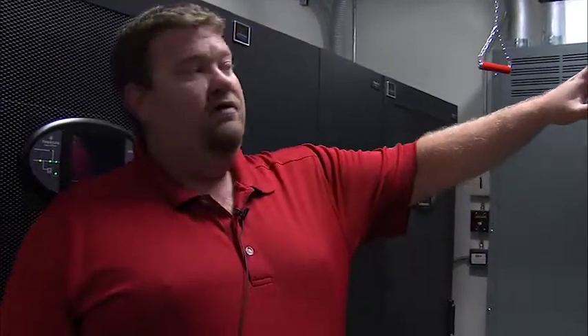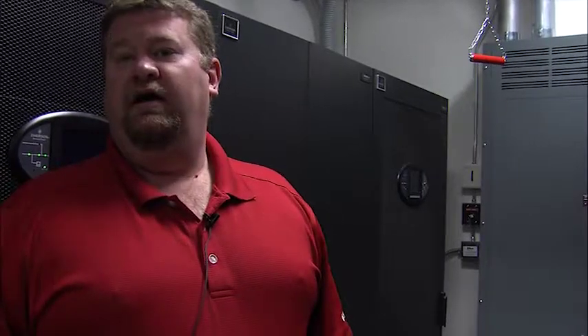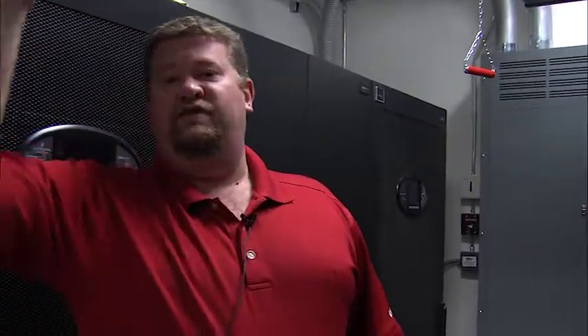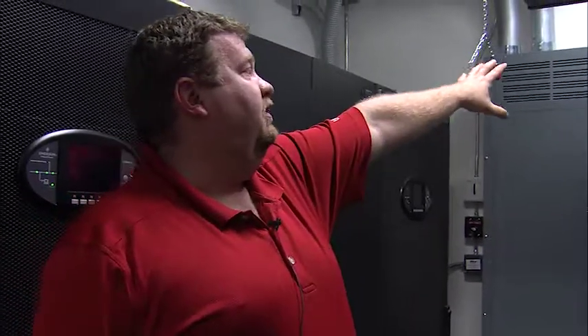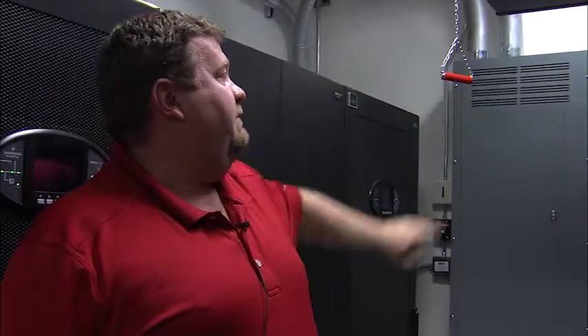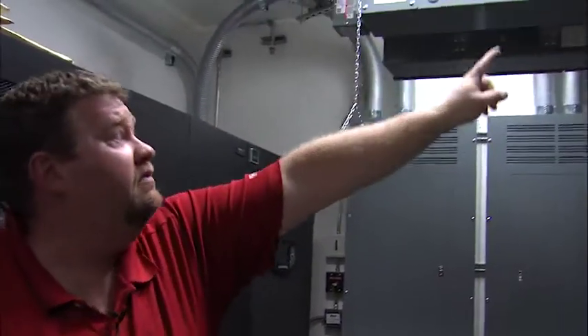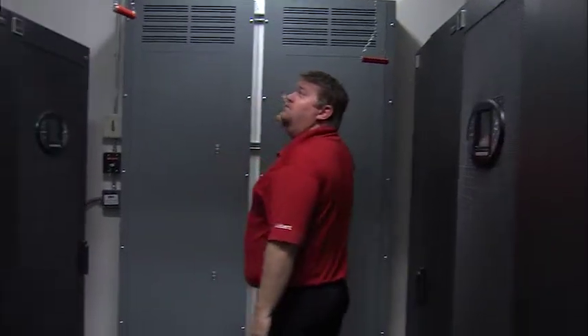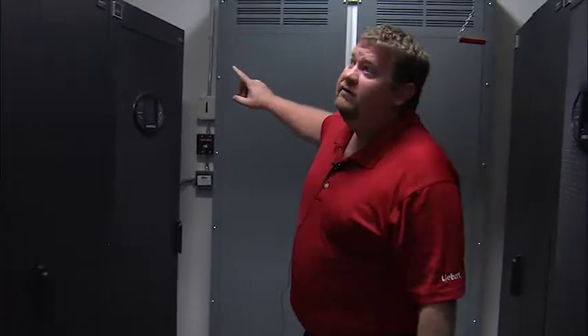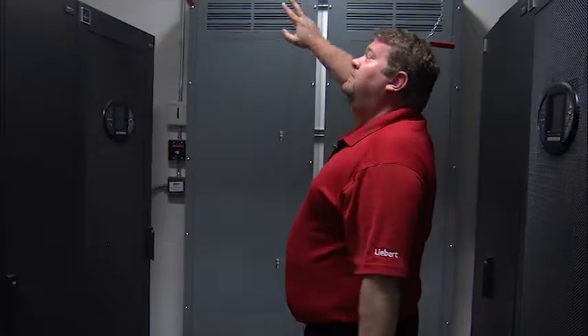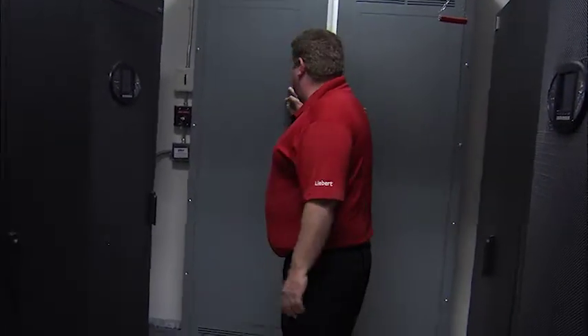At that time, when these are in bypass, we have wrapped around this system. These are the input. These will never get pulled unless in an emergency. Again, these will always feed. These are feeding the power of the units. Once we have these pulled, then we're wrapped around. We're wrapped around the unit, and we're feeding out into the wraparound bypass panels.